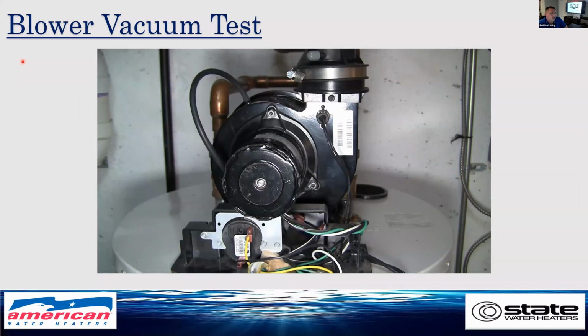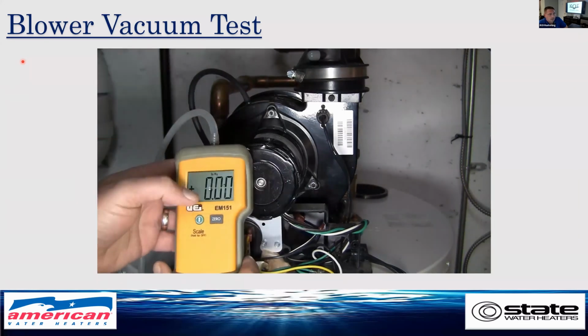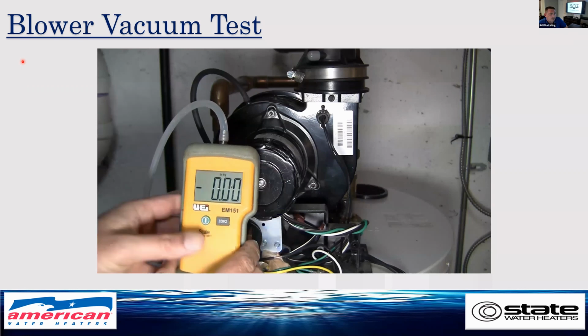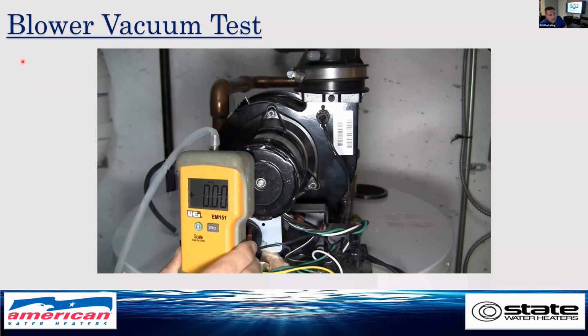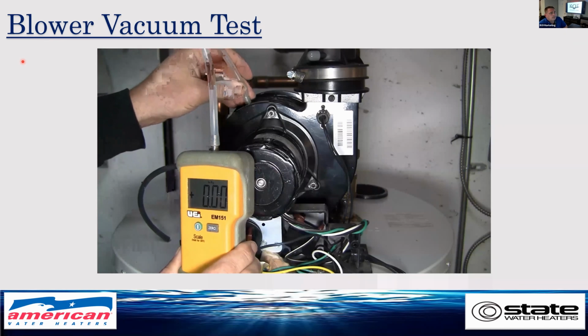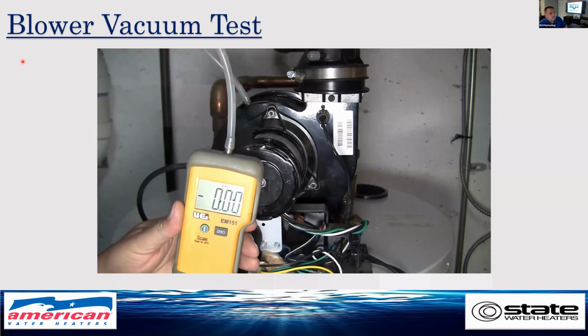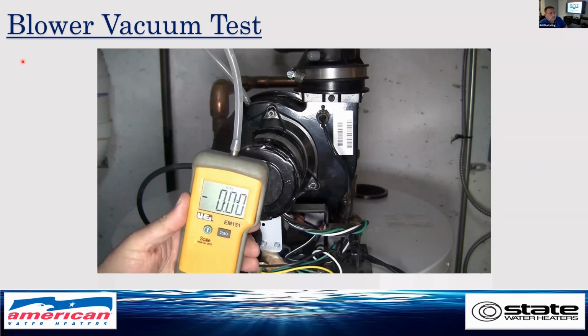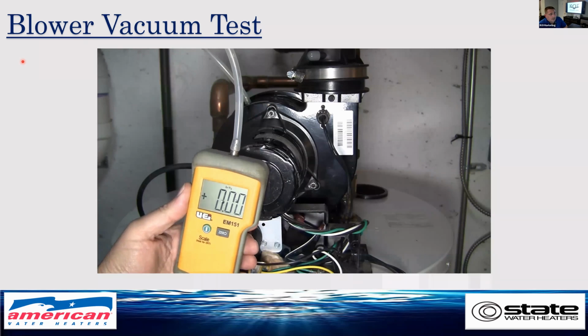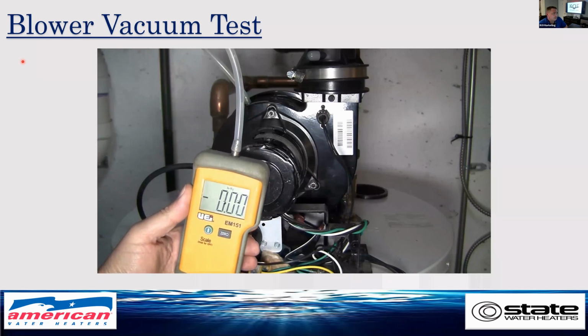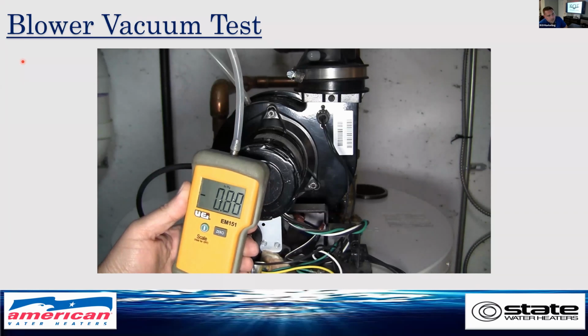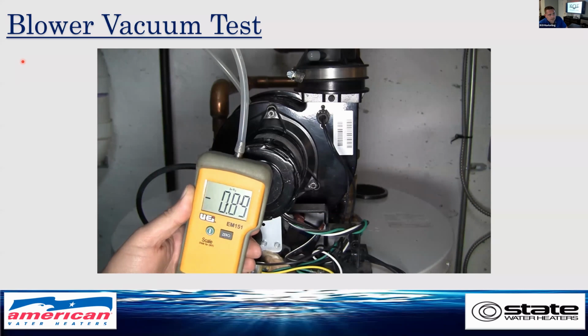So, blower vacuum test. That is a manometer. Make sure my setting is in inches water column. I zero it out. We remove the vacuum hose. Turn my blower on or gas valve on. And you see we have a reading of negative 0.88. And on that particular unit, it's a negative 0.27 to engage it.